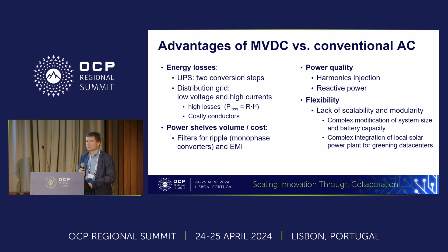If you have a look at the conversion losses, on the left side you have the approach of today. So we have the grid, then there's online UPS, so we have 2 times 2% losses there. Then there's a separation transformer. Then it goes into the power shelves. Here we have 3% for the power shelves. And then the green box, this is the rack. There are the power shelves with 3%, and then it goes to the microprocessors.